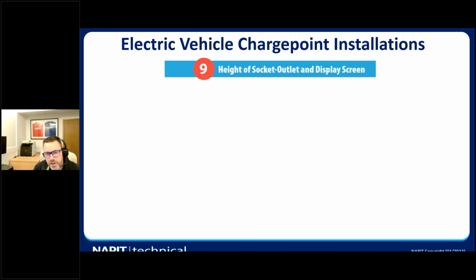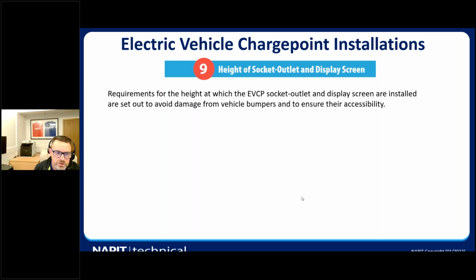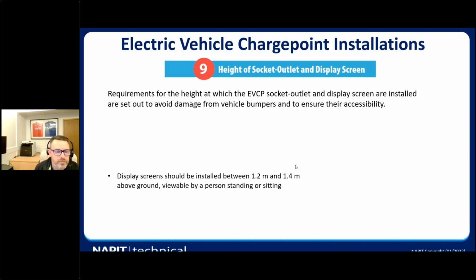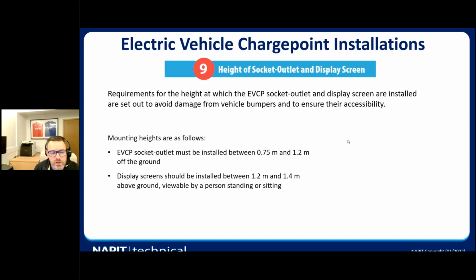Number 9 is the height of socket outlets and display screens. The requirements for the height at which an EV socket outlet and display screens are installed are set out to avoid damage from vehicle bumpers and to ensure accessibility for people using EV charge points. The mounting heights are as follows: EV socket outlets should be installed between 0.75 and 1.2 meters off the ground, and display screens should be installed between 1.2 m and 1.4 m above the ground, so they're viewable for a person standing or sitting using the EV charge point.